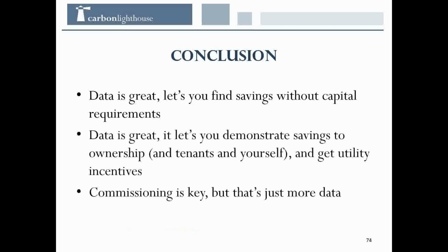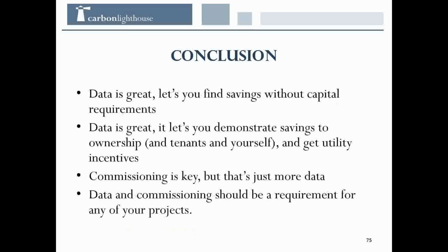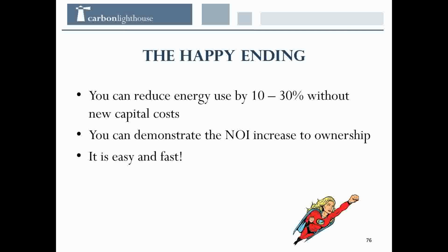So I've turned into kind of a data evangelist here - I should have warned you about that up front. I would argue that data, commissioning, and measuring things should be a requirement for any energy efficiency project. But the wonderful thing is you can reduce energy use by 10 to 30% without new capital costs, and you can demonstrate this increase in net operating income and decrease in utility costs pretty easily with the data, if you do good measurement and verification.